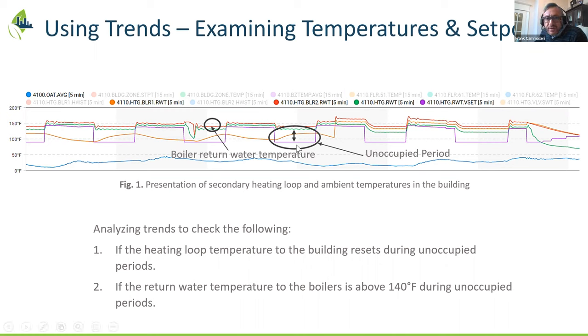So on the first point, this is the unoccupied periods. The purple line here is the set point of the building loop - this is the water temperature going into the building. The set point does go to 90 degrees, which is great - that's the purple piece. But the actual temperature of the loop, this green line, you can see it doesn't reach that.